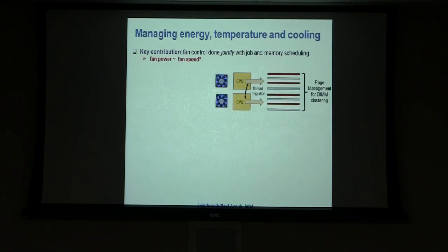Going forward, as I mentioned, fans are there and you want to use them effectively. The problem is that fans today operate only as a function of the thermal sensors -- they're completely oblivious to any kind of workload scheduling and management. Fan power is cubically proportional to fan speed, so for every notch up in fan speed, you're paying a lot more in terms of energy.